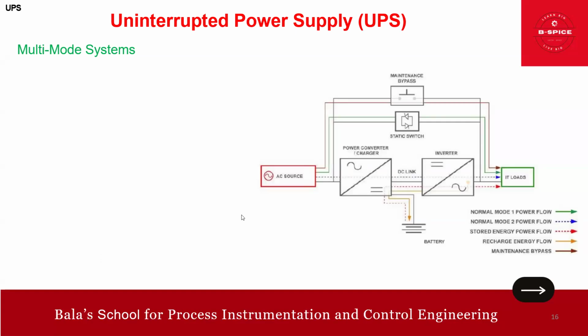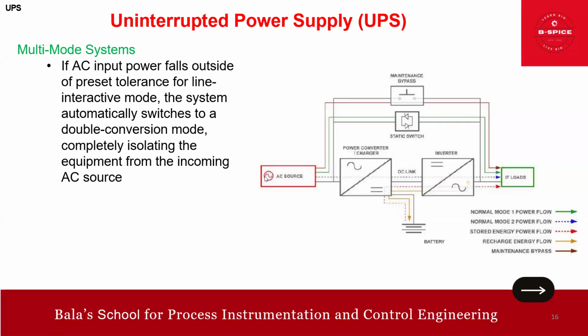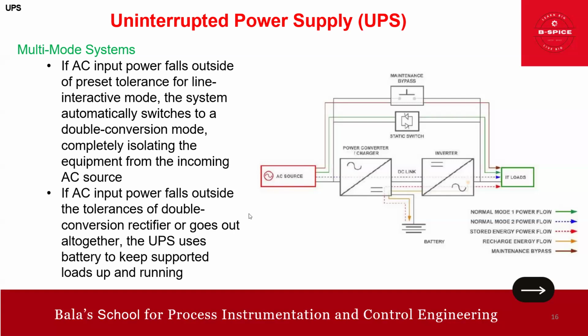Now, if power fails, the system automatically switches to double conversion mode, completely isolating the equipment from the incoming source, so that the power is very clean. If the AC input power falls outside the tolerance of the double conversion rectifier, or goes out altogether, the UPS uses the battery to keep the supported load.